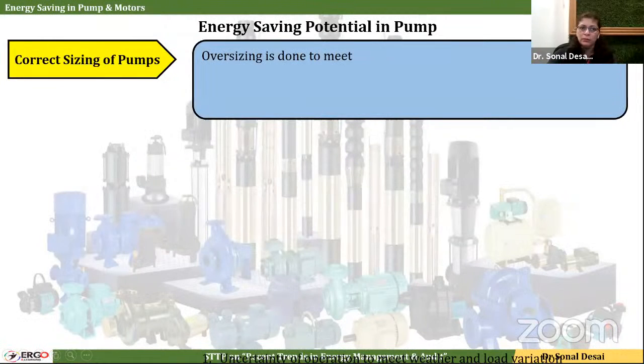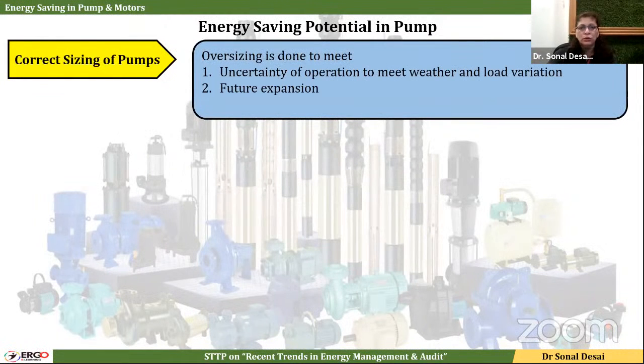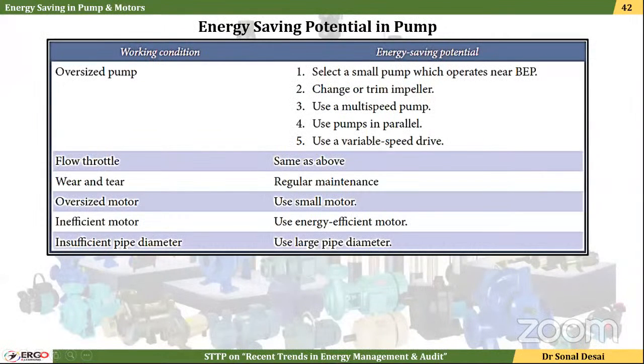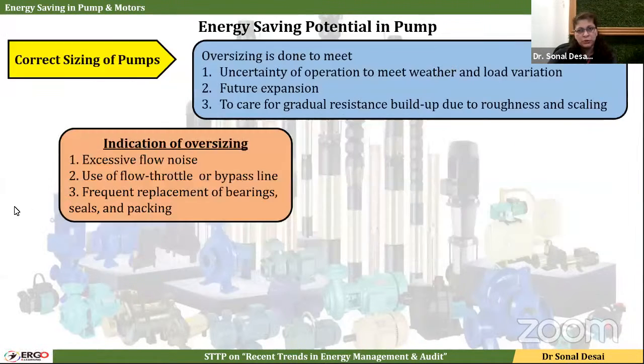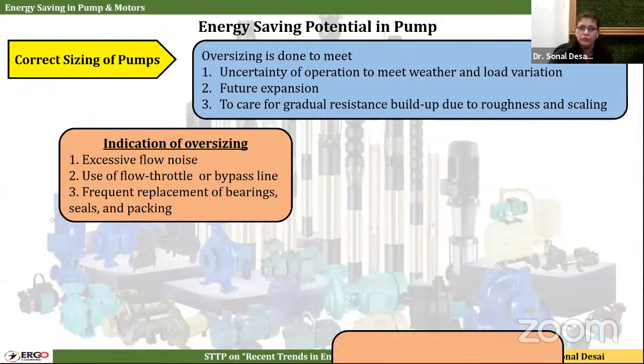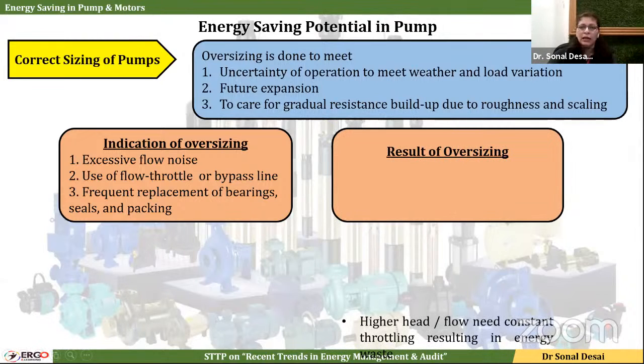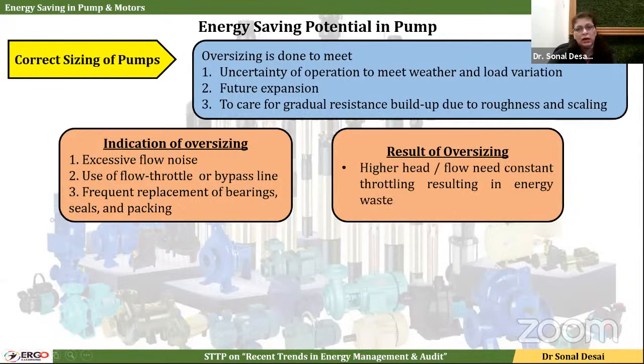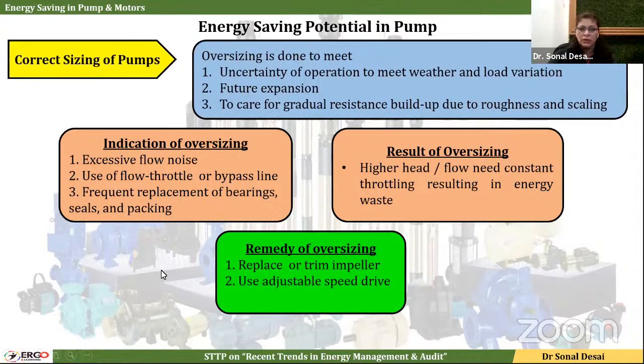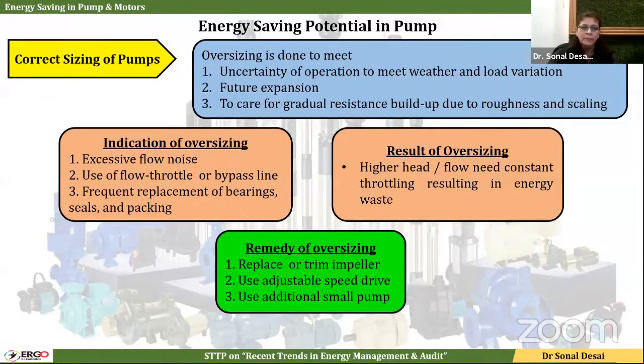So correct sizing of the pump plays a very important role. Don't look only at the present need when deciding the pump. You come to know that a pump is oversized when there is flow noise, when there is throttling, when there is a bypass, when there is frequent failure of bearings. These are all indications of oversizing, resulting in higher head or continuous throttling of flow. So replacing the impeller, a speed drive, or a smaller pump are the remedies.